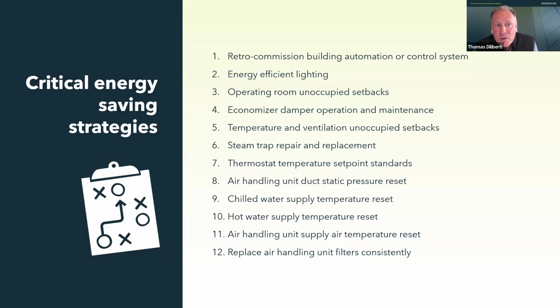What's happening during those hours when operations are not taking place? Are you able to take the temperature of that space and set it back? A big one is the airflow in that space. Operating rooms require a tremendous amount of fresh air being pumped into them, but when nobody's there during that unoccupied time, systems can be set to reduce the amount of outside air flowing in. It's a huge opportunity for savings that tends to get overlooked. If you've never thought of that, you might start exploring it. That's a whopper. There's a great opportunity there.